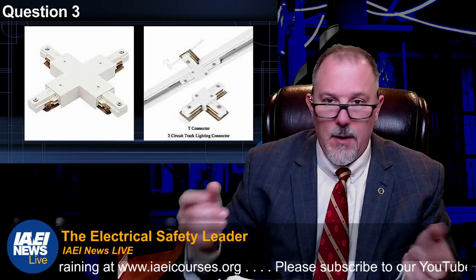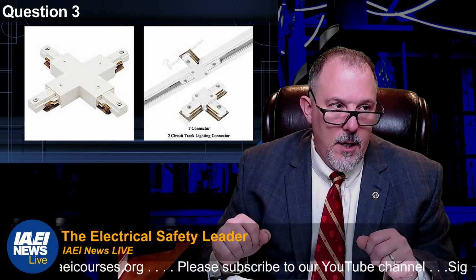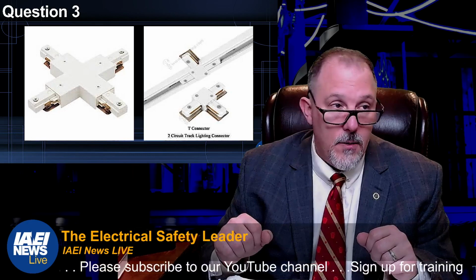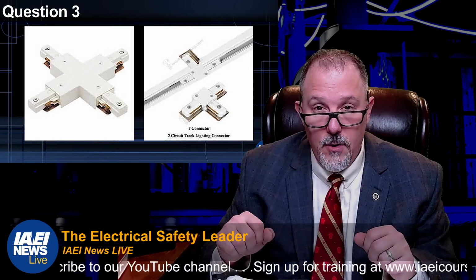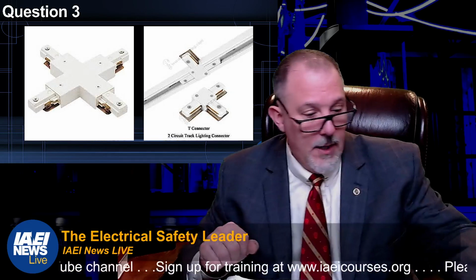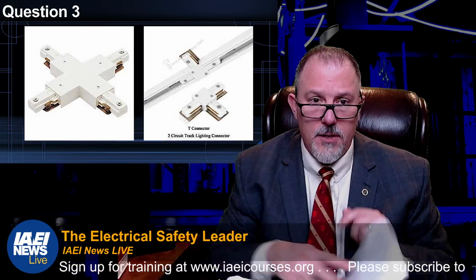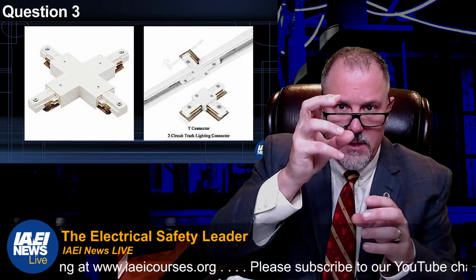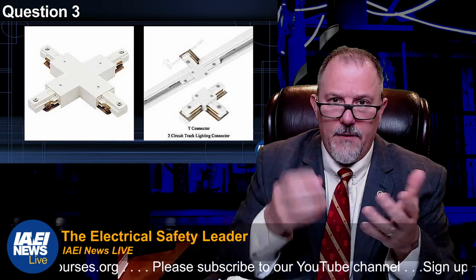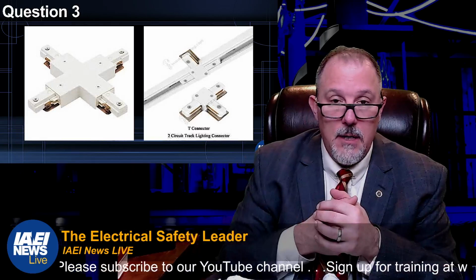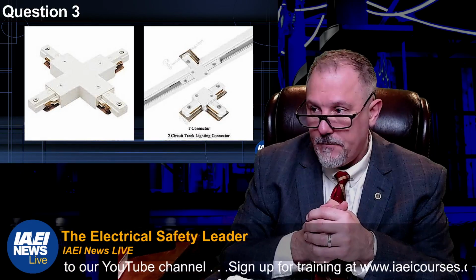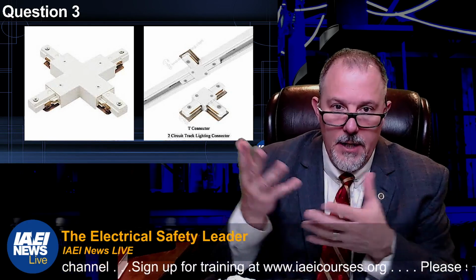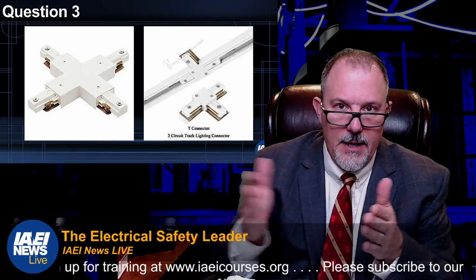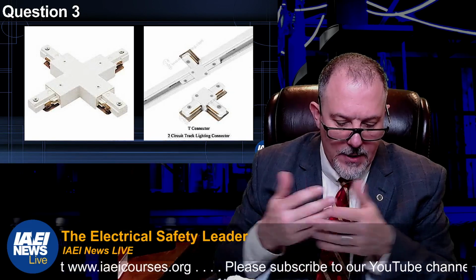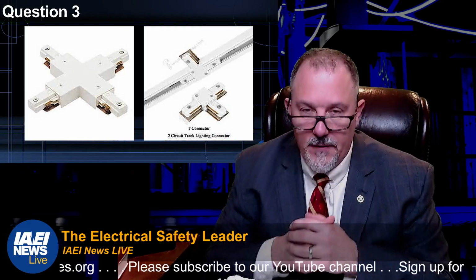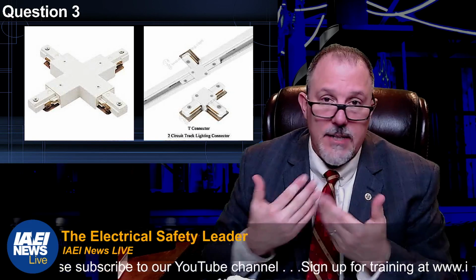So if I have a track lighting and I'm putting those portable fixtures on it, here's the question. Do you call that a luminaire? You can't call it a lamp, because the lamp would be the device, the bulb or whatever that you put inside to produce the light. So I'll call it a luminaire because it is an assembly, and the way it's mounted and wired into the circuit is through this track lighting. And I could put multiple fixtures on it. If it's a 2-foot section, I could put multiple fixtures in there. And what they require is that for every 2 foot, you have to add another 150 VA to your load calculations. Not something the manufacturer can do for you.